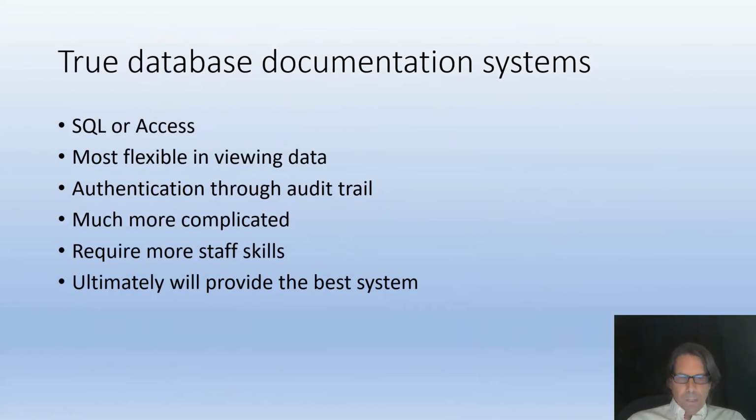So the real most advanced system is a true database system to document all of your site activities. And this would typically be using SQL or Access database. It really is the most flexible in viewing the data however you like to view it. The authentication is a lot easier. It is much more complicated and it requires more staff skills, but it probably would provide the best system in the long run, especially for larger organizations and organizations that have multiple sites and are typically moving instruments around fairly often. This is really the right approach.